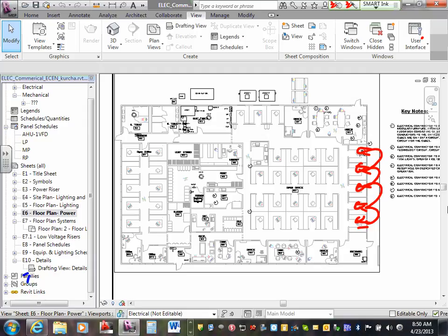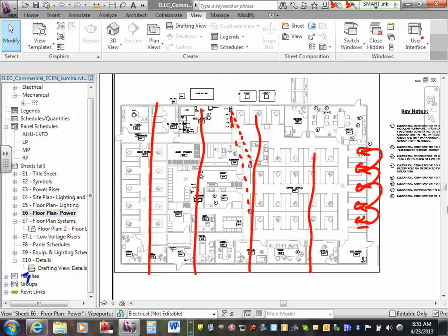And then you might have to build a conduit system, depending on where the receptacles are in the floor. So let's assume we decided that we're going to go in the floor. That's going to be a home run directly from each one of these to the box. You're going to take these as underground ones, PVC conduit, underground, that's how we wired it. The rest of them, guys, I don't want to move right through the wall. So we're going to grab them and build the same thing, a conduit system in this area, and when you're done with this circuit, you can come directly and tie it to the closest gearbox that you have.